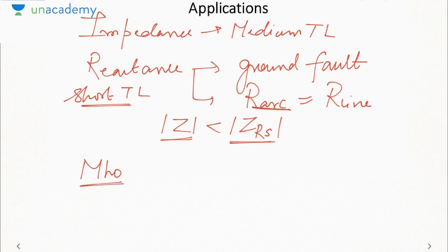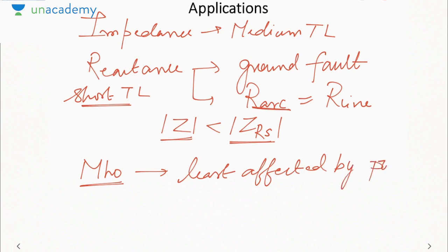The last type of relay is the Mho relay, and the property of the Mho relay is that it is least affected by power swings. We studied surges and transients on a transmission line, particularly for a long transmission line. Hence it is used for protection of a long transmission line. This is one of the most commonly asked questions in PSU examinations: what is the method of protection of a long transmission line? We use the Mho relay. They can also ask it the other way around: where will the Mho relay be used? It will be used for the protection of a long transmission line. So remember: short line, impedance; medium line, reactance; medium line, impedance; short line, reactance; and long line, Mho relay. These are called distance relays.